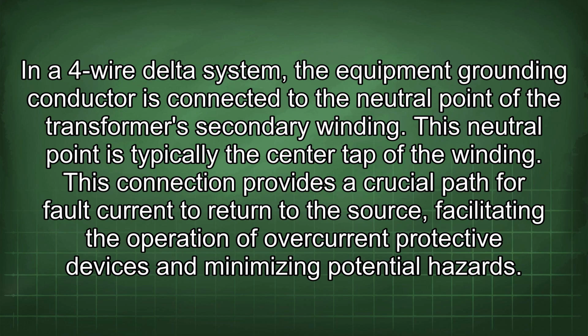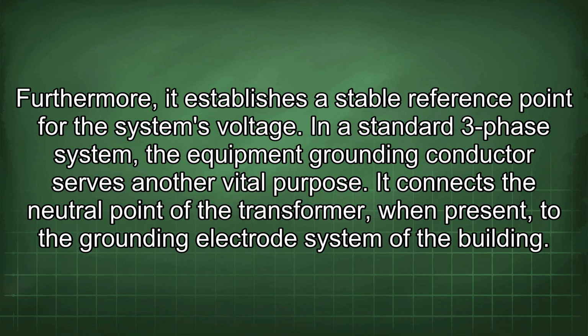This connection provides a crucial path for fault current to return to the source, facilitating the operation of overcurrent protective devices and minimizing potential hazards. Furthermore, it establishes a stable reference point for the system's voltage. In a standard 3-phase system, the equipment grounding conductor serves another vital purpose. It connects the neutral point of the transformer, when present, to the grounding electrode system of the building.